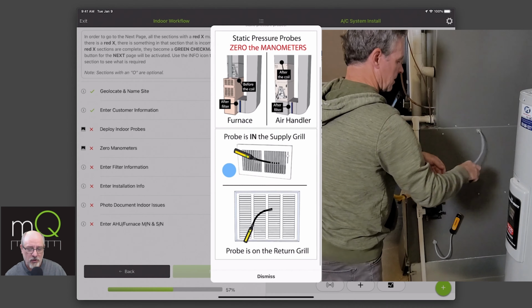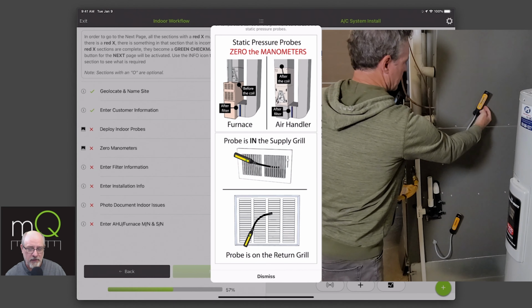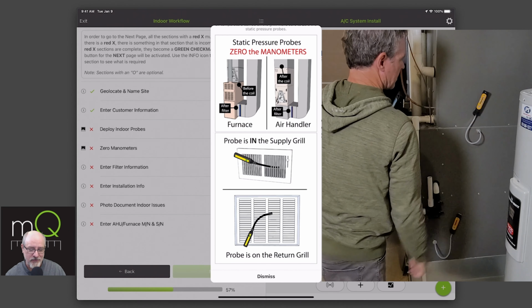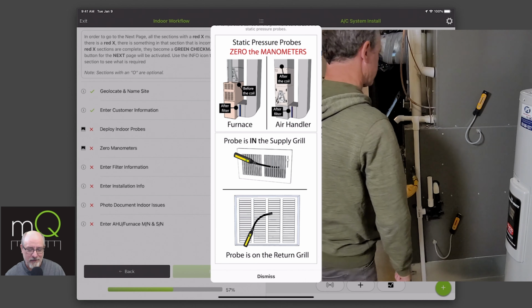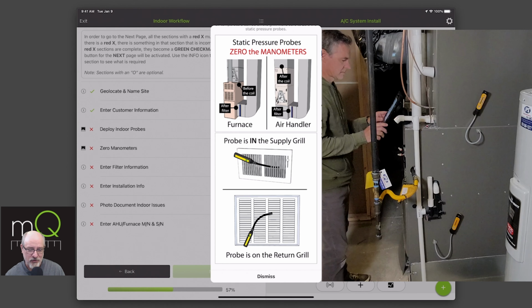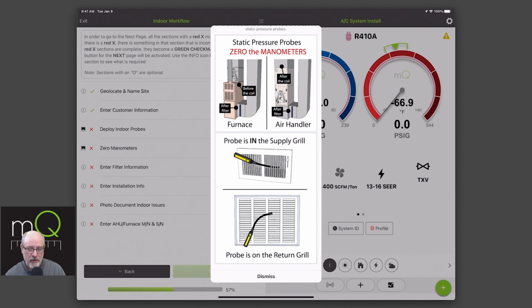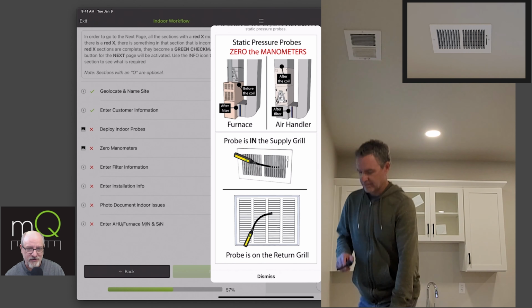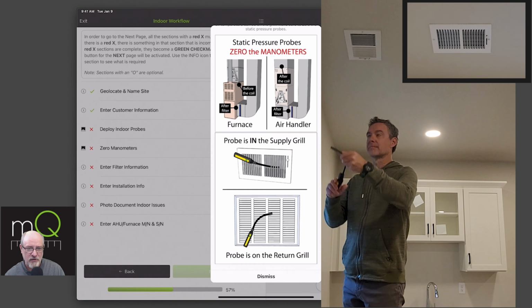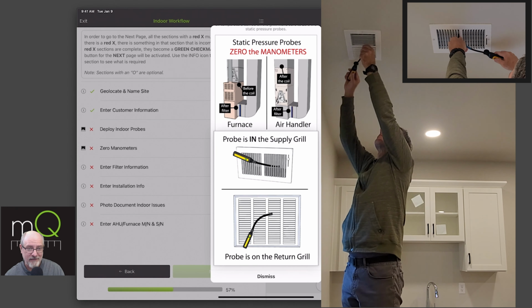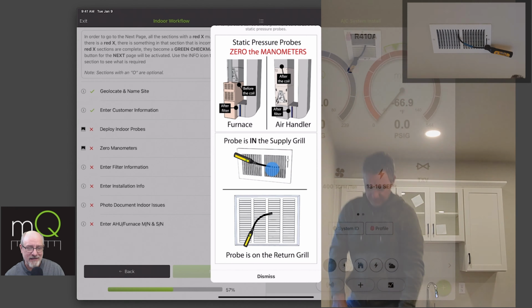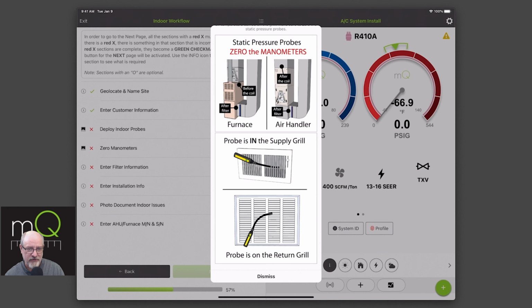We're also going to install the supply and return psychrometers, or hygrometers. It's a universal concept here, but we're mostly measuring temperature and humidity. It's important that the probe is in the supply grill nearest the air handler, so it's not in the air handler, it's not in the plenum, it's actually in the system, in the grill. Notice the detail here where you actually put that probe inside the actual grill. It cannot be on the face for the supply. The return, it can be.